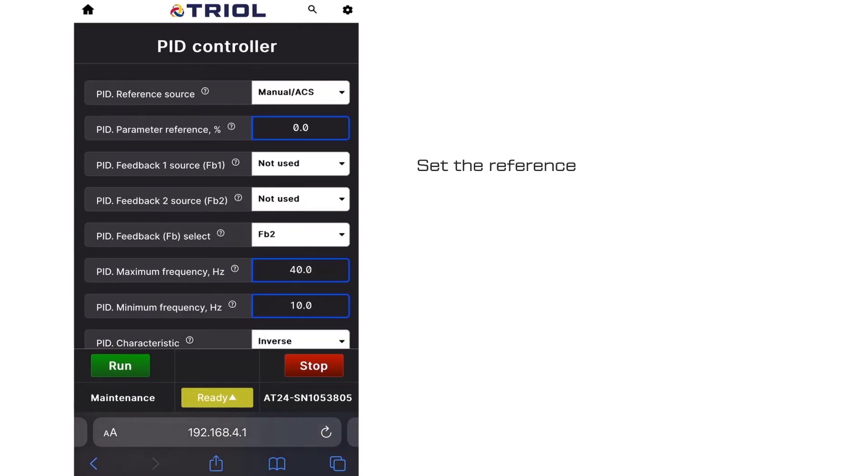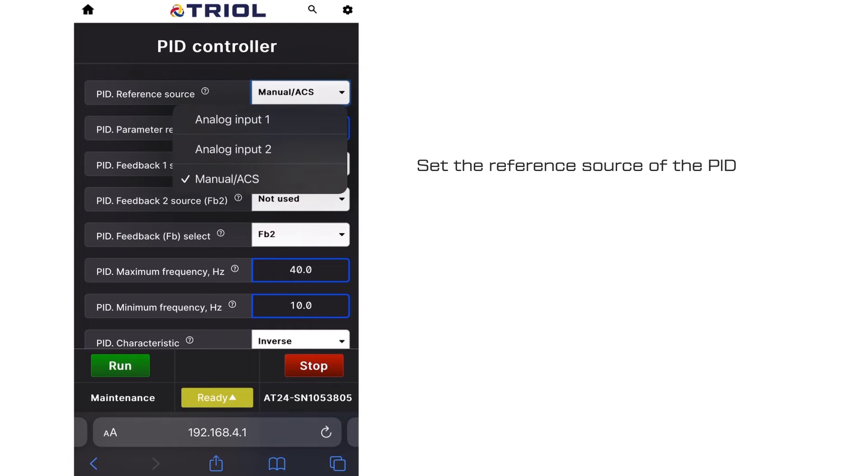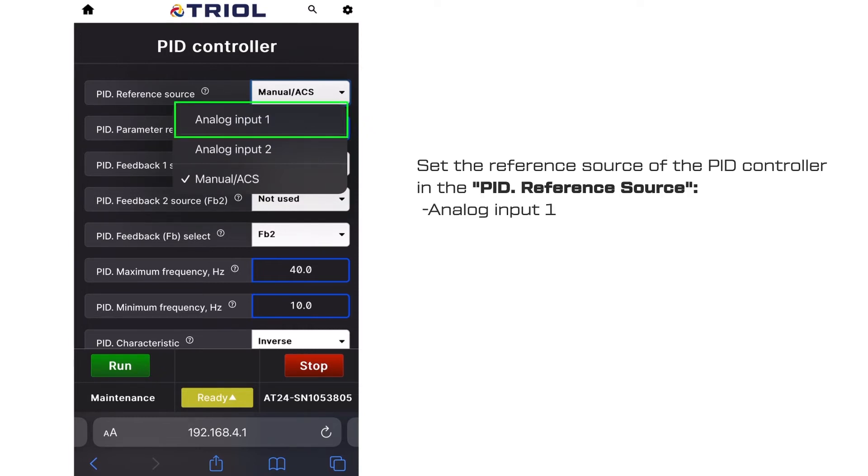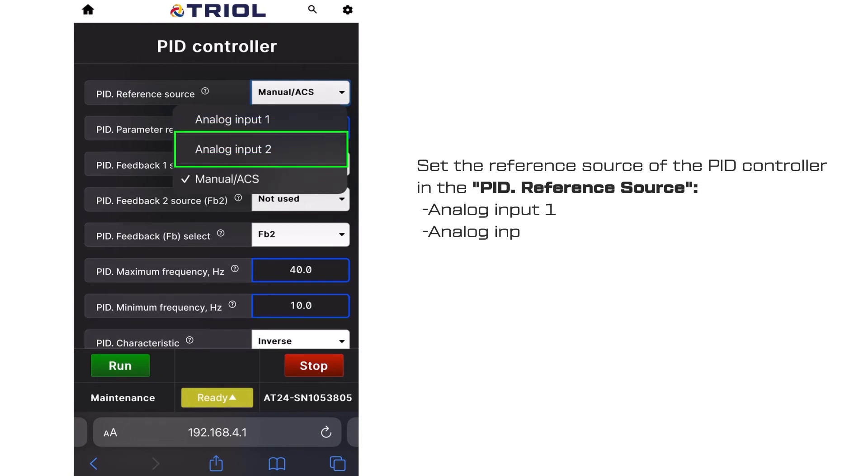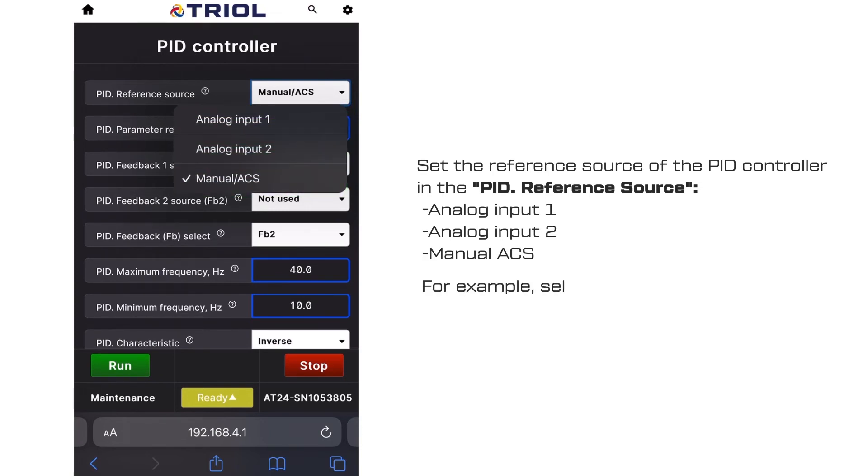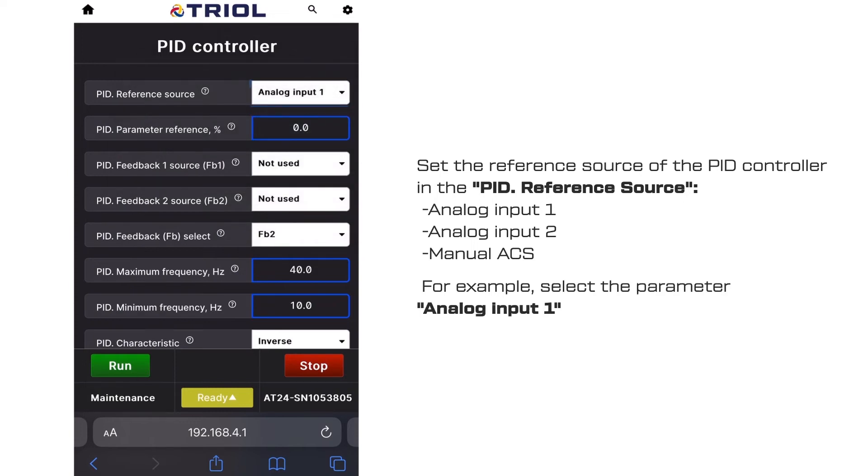Set the reference source of the PID controller in the PID reference source: analog input 1, analog input 2, or manual ACS. For example, select the parameter analog input 1.